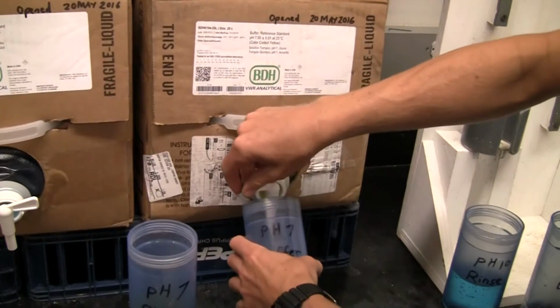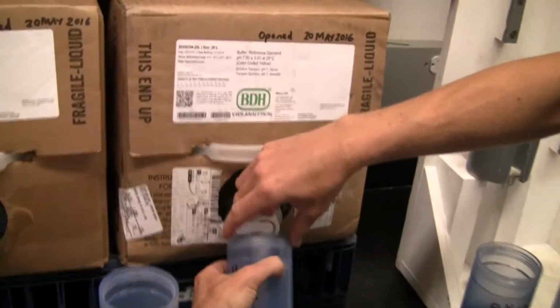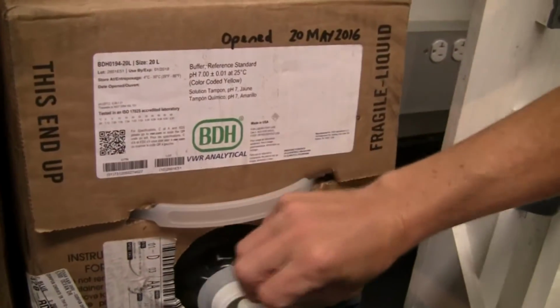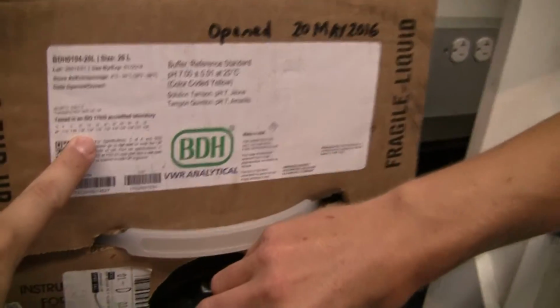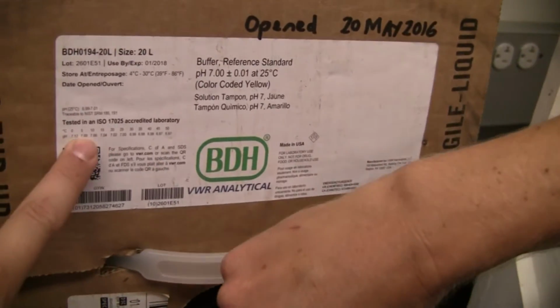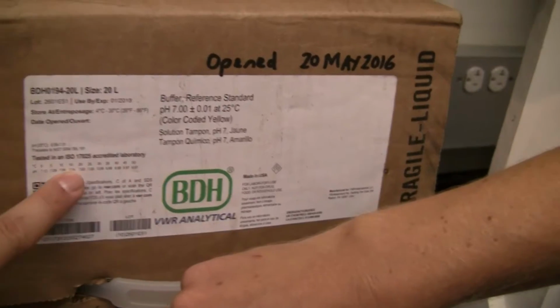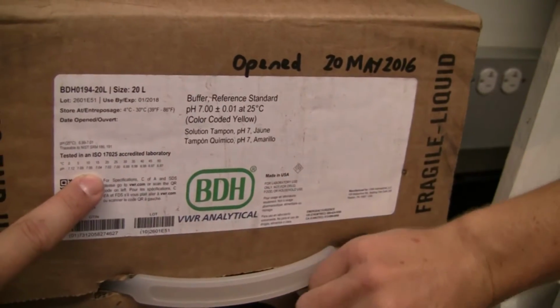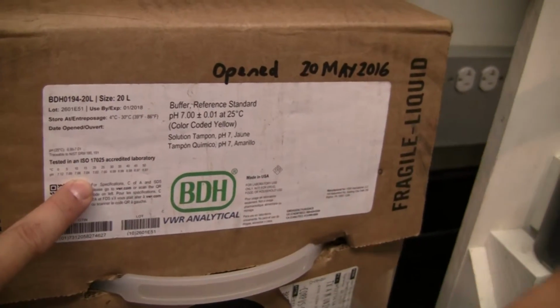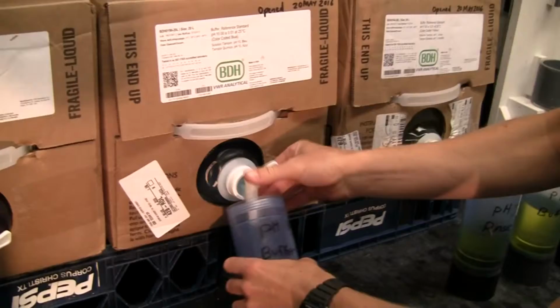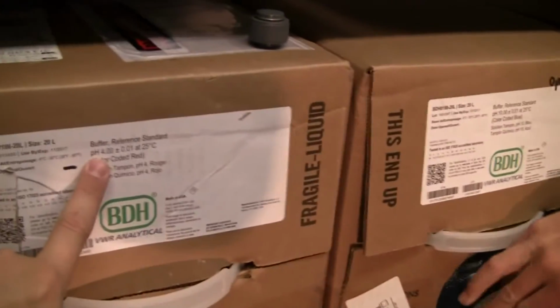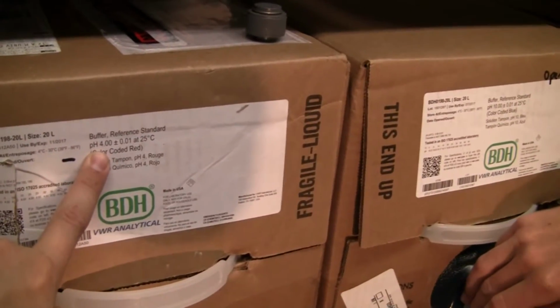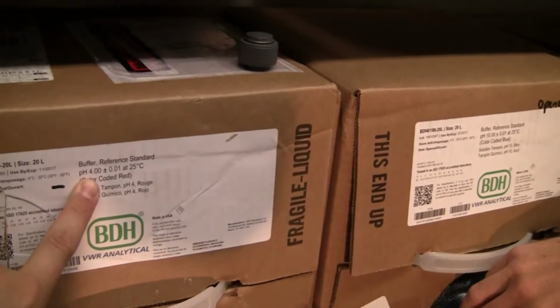So we're going to be filling up our buffer containers. This is the pH 7 standard, and with pH, the standard actually changes with temperature, so there is a temperature table right here that shows you what the value of the standard is depending on what the temperature is out in the air. So you'll need that for calibration. Here we're doing just a two-point calibration, but if you're using a three-point calibration, we do have pH 4, which would require 2 more cups for a buffer and a rinse.